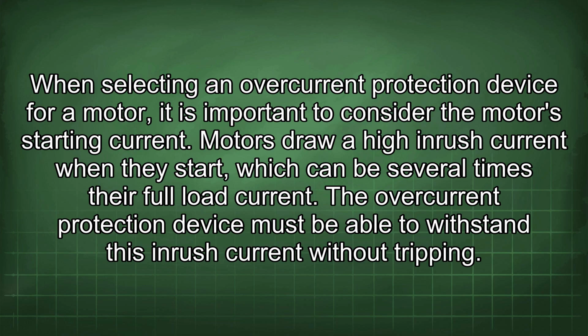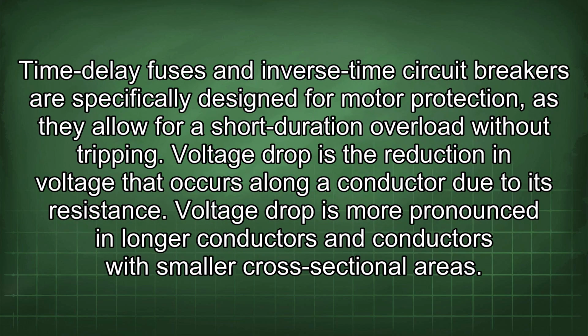When selecting an overcurrent protection device for a motor, it is important to consider the motor's starting current. Motors draw a high inrush current when they start, which can be several times their full load current. The overcurrent protection device must be able to withstand this inrush current without tripping. Time delay fuses and inverse time circuit breakers are specifically designed for motor protection, as they allow for a short duration overload without tripping.